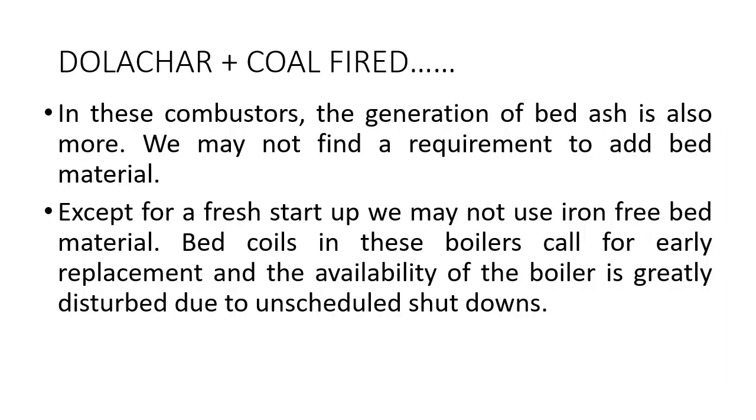In these combustors, the generation of bed ash is also more. We may not find a requirement to add bed material for a long time. Except for a fresh startup, we may not use iron-free bed material. Bed coils in these boilers call for early replacement and the availability of the boiler is greatly disturbed due to the unscheduled shutdowns.